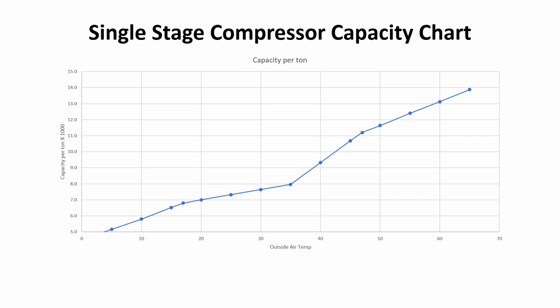This is a single-stage compressor capacity chart. And we can see it's pretty much linear. The warmer it is outside, the greater the capacity of the system. There's this little knee here, often referred to as the defrost knee, because when the system is in defrost, obviously the capacity per hour goes down. This is a very traditional capacity curve.